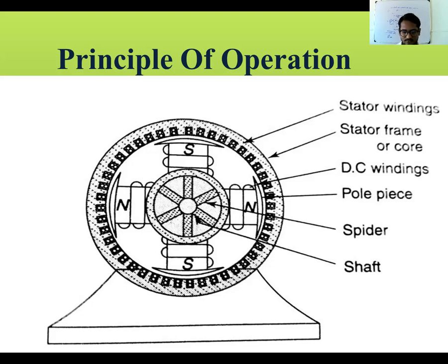With the armature winding, it has various parts like stator frame, stator core, and cooling arrangements. The frame may be cast iron or steel. The stator core is made up of high-grade silicon steel laminations, whereas the three-phase winding is put in the slots of the stator and is generally connected in star fashion.